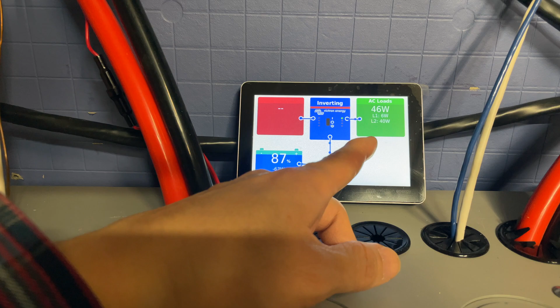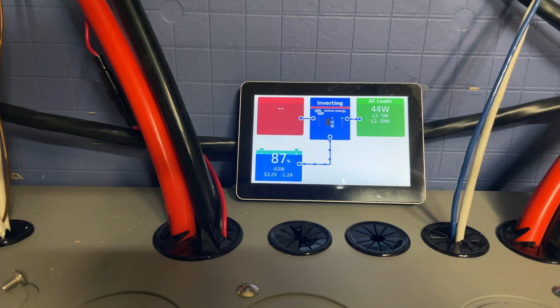So in this case, the maximum line imbalance this is going to be able to handle is, let's say, up to 3,000 VA, mainly because that's the size of this inverter. But if you wanted to draw, say, 2,000 watts from one inverter and nothing from the other, you won't have a problem with that in terms of it being able to handle it. You will have an issue trying to maximize the output of your entire system, because you're going to be capped at that. So if you're wiring it to a load panel, keep that in mind, because the smallest inverter is going to be the weakest link in this kind of case. But if you're worried about big single-phase devices coming on and off line, that's going to be a small problem, but not really a problem in this type of system. So that's another beauty of this type of system.